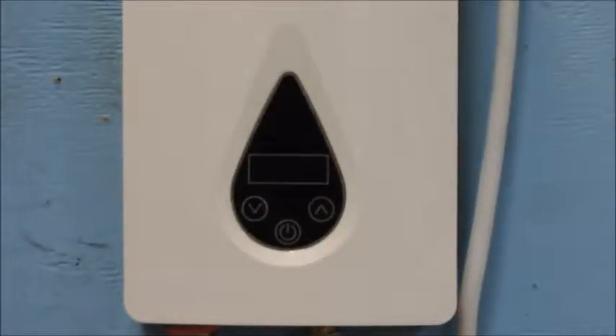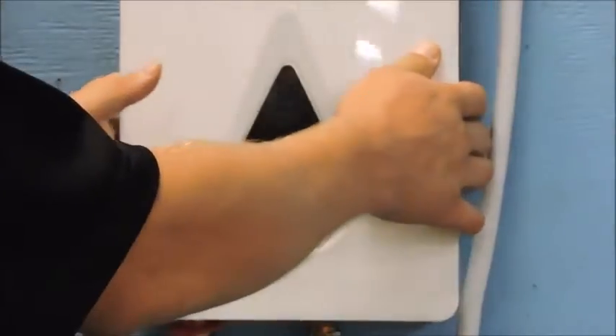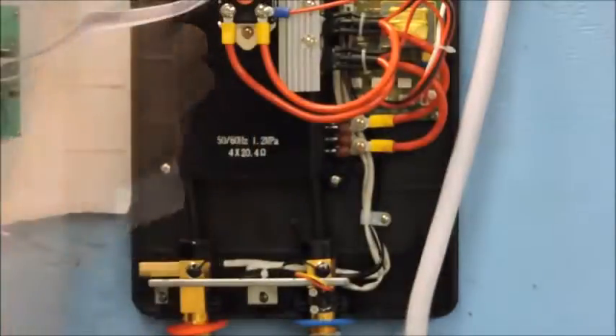An E3 error code indicates a temperature sensor failure. This failure can occur either at the inlet or the outlet temperature sensor. Majority of the time it is the outlet temperature sensor that has failed. It is located on the left of the water heater on the front of the outlet fitting, as seen here.